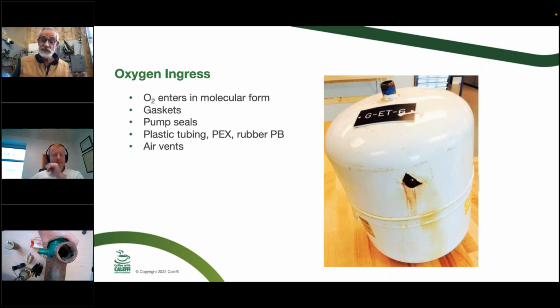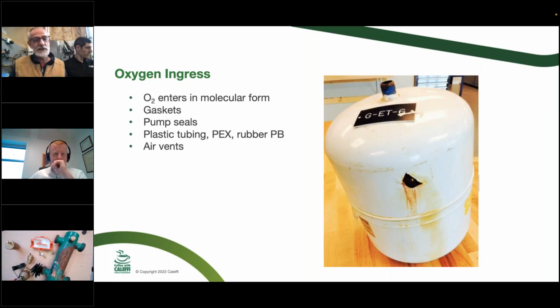And this was on a system that didn't have a fill system. It had a fill tank on it. So they said it wasn't taking on water. It's not like there's a leak somewhere. Every day a gallon of water was going in the system. It was a completely sealed off system. So all that corrosion that you see in there happened from the oxygen getting through the tube into the system, and it went through a bunch of expansion tanks. This contractor that put this in, he said, I'm not the first one that worked on this. He said, I could tell by the expansion tanks that had gone through it, that were laying around the room there. So that's why we want to make sure that we've got an air and oxygen tight system as best we can.